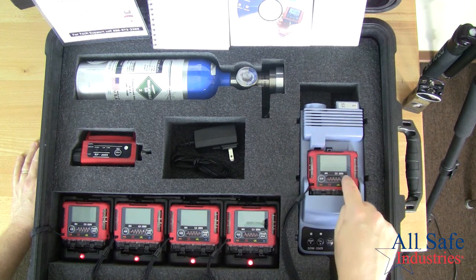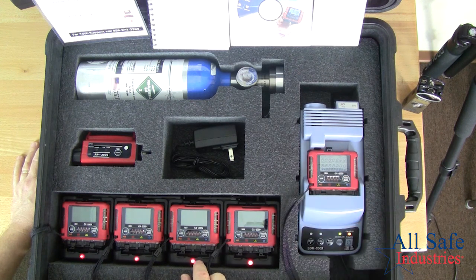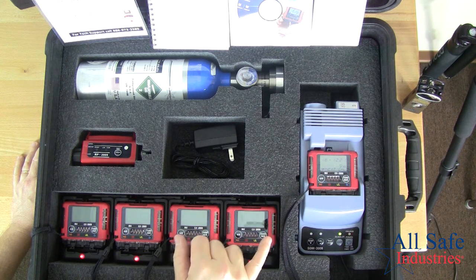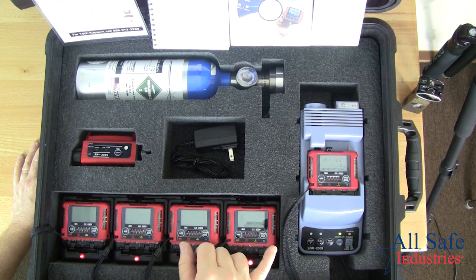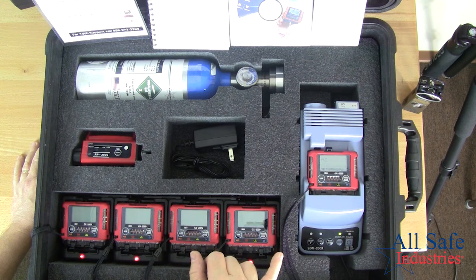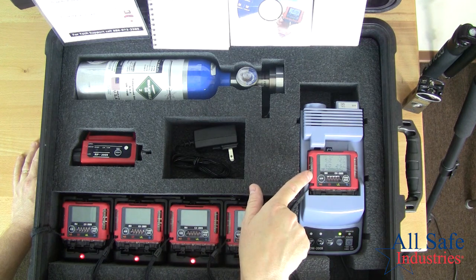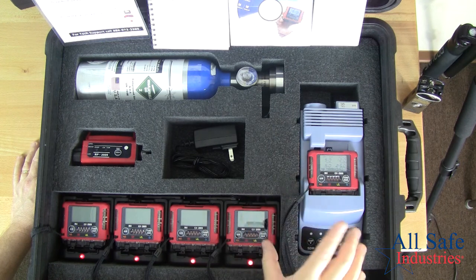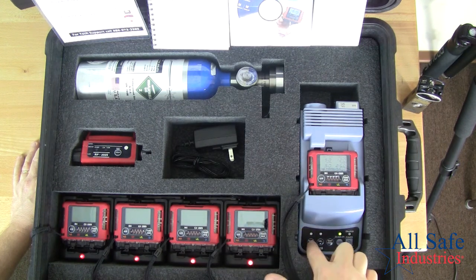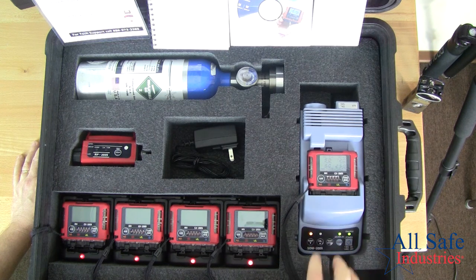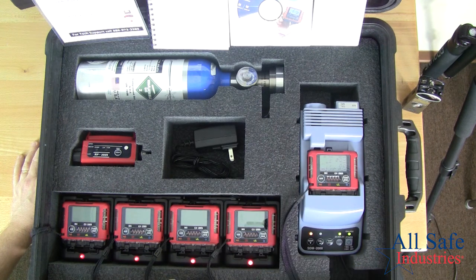So if I turn the meter on while it's in the cal station, it will start its normal boot up sequence, but then it will recognize that it is in a cal station and it will say PC transmit, just like that. And so now it knows it's in a cal station, and so I can reach over here and press the bump button, hold it for a second, and then you'll hear the pump start to run, and it will automatically go and do a bump check on that instrument.